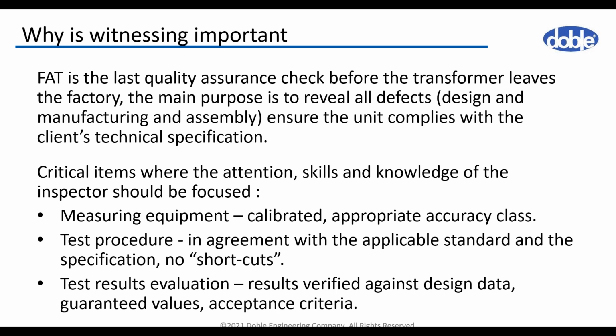The result should comply with the design data, and also with the guaranteed value and acceptance criteria. In case we find a significant deviation in this data, this is an indication there are some defects, most likely during production.